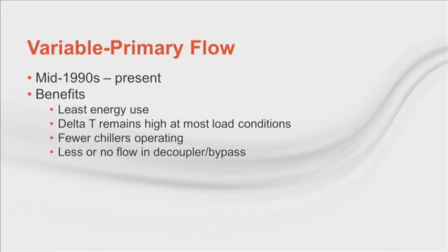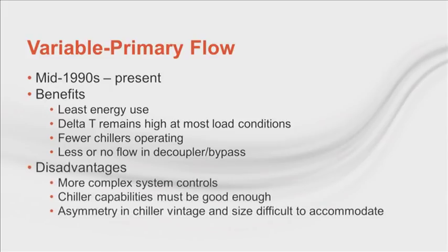Modern chillers are capable of operating with variable flow without nuisance trips, provided the system controls are done properly. The most attractive benefit is that a new system costs less to install, 3 to 8% less, and it has 3 to 5% lower lifecycle cost. DeltaT to the chillers remains constant until minimum flow bypass is necessary. This allows the chillers to be fully loaded before additional chillers are staged on. Cooling energy is not pumped unnecessarily. The disadvantages of this system configuration include system controls complexity, older chiller capabilities, and how to accommodate varying sizes and vintages of chillers. So let's first talk about system control.